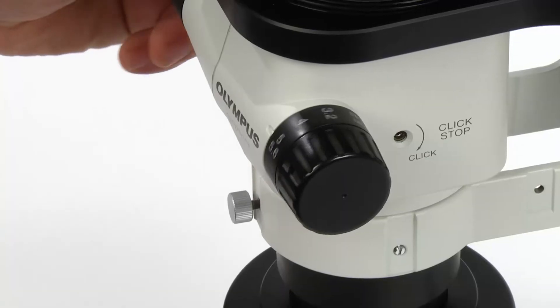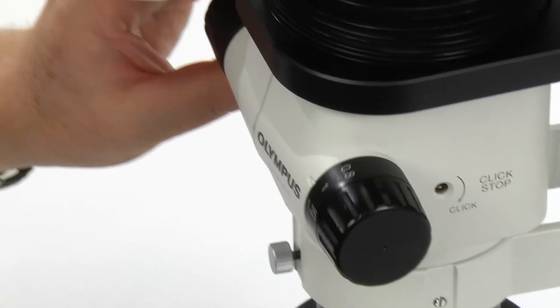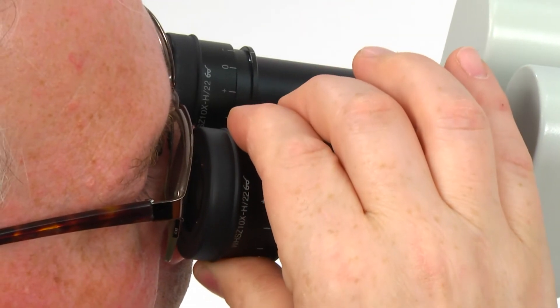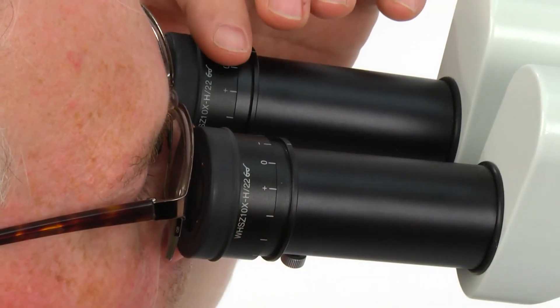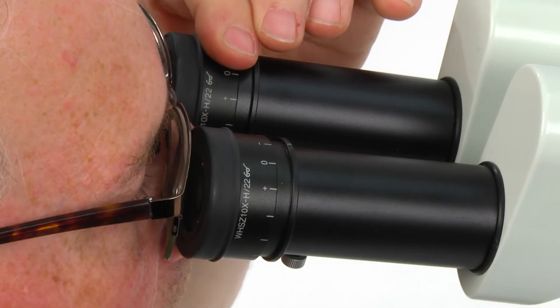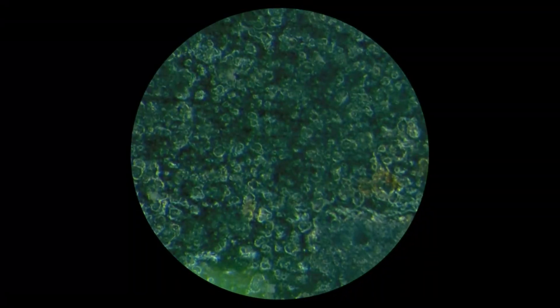Finally, set the zoom adjustment knob for the lowest magnification and rotate the diopter adjustment ring of the left and right eyepieces to bring the sample into focus. The adjustment is now complete and the image should now remain in focus from low to high zoom magnification.